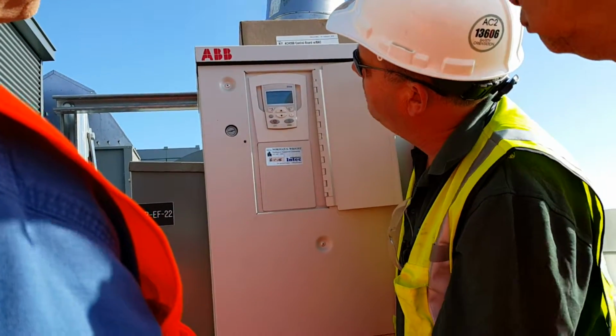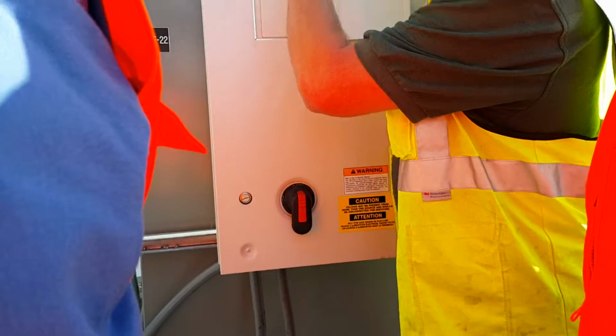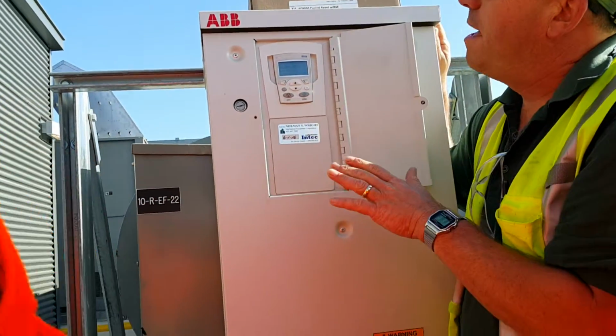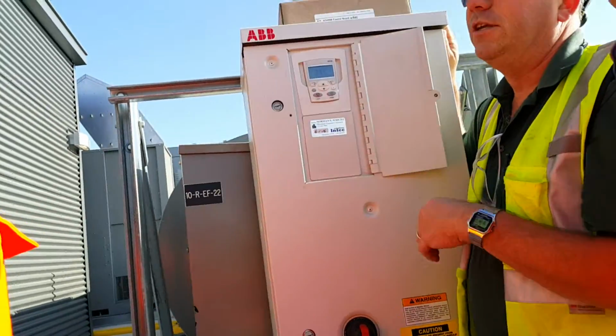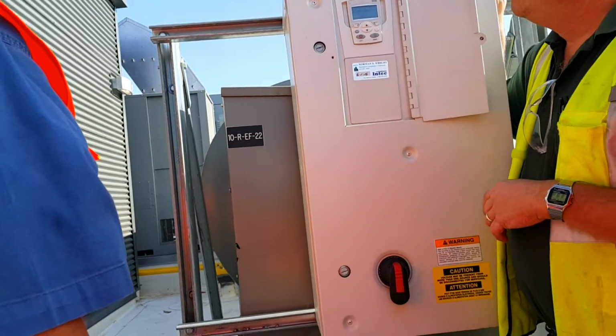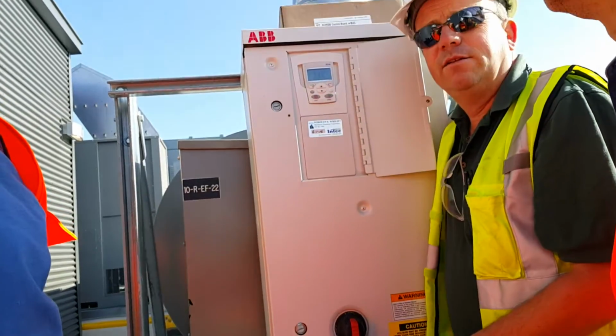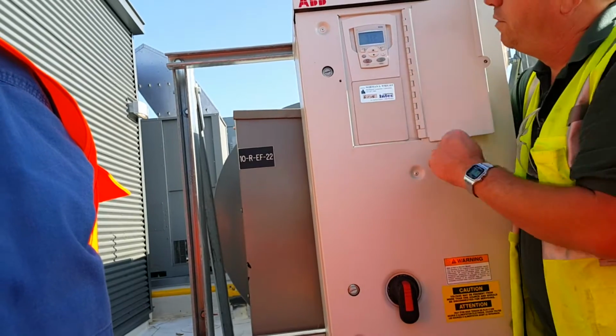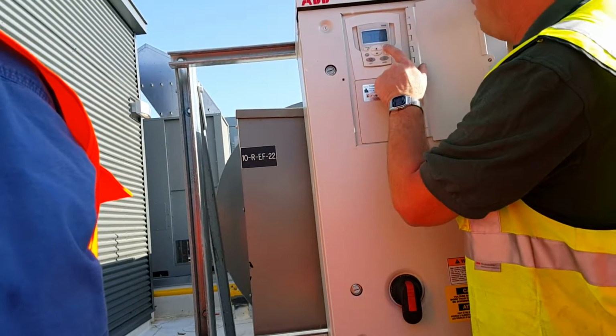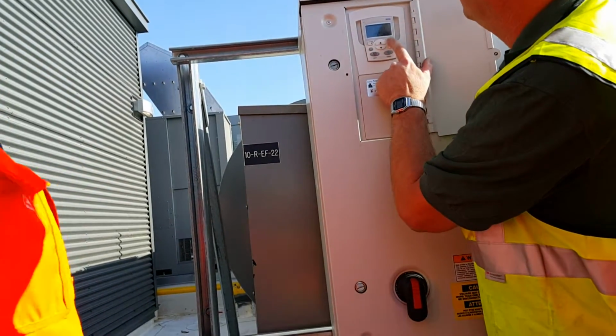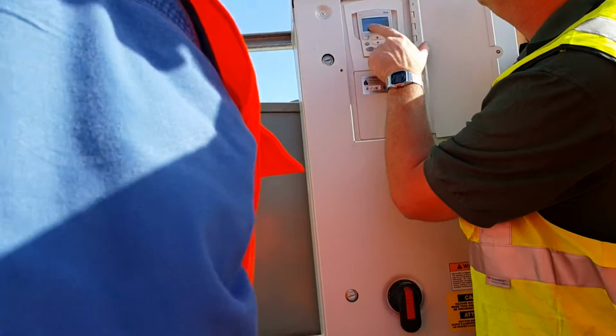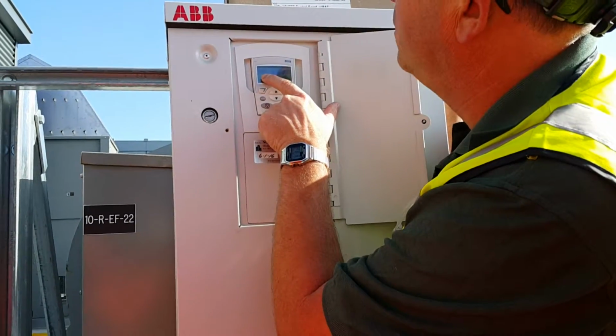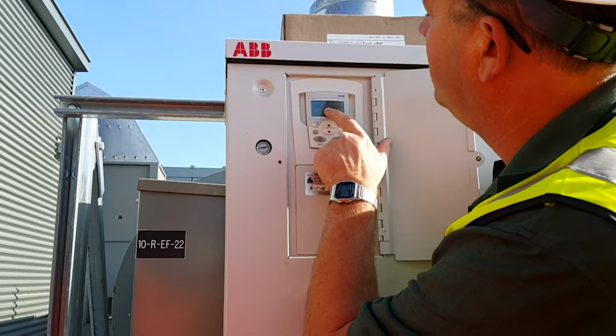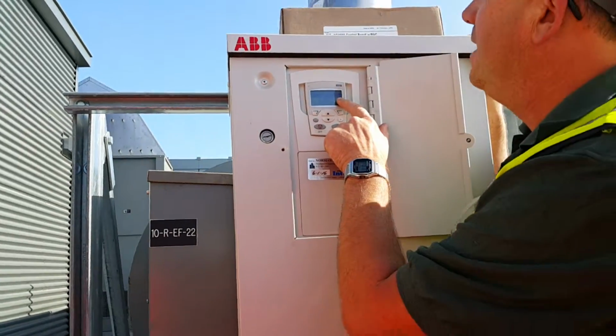Trying to keep itself alive. Okay. You can see the red light. It says fault. This is a fault that automatically resets. There she goes, right back up again. It'll also reset if it dies all the way off. So now you saw what a fault looks like. If we were to look at the fault logger right now, it'll say again DC undervoltage fault, 6/30/2016 at 8:16.